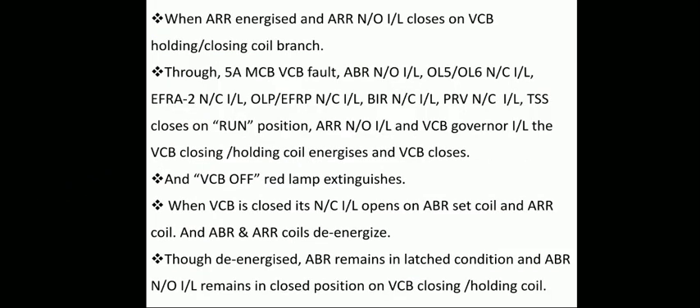When ARR energizes, its normally open interlock closes on the VCB holding and closing branch, parallel to the VCB normally open interlock. Through the 5-amp MCB for VCB fault, ABR normally open interlock, OL5 and OL6 normally closed interlocks, EFRA2 normally closed interlock, OLP and EFRP normally closed interlocks, BIR normally closed interlock, PRV normally closed interlock, TSS closed on run position, ARR normally open interlock, and VCB governor interlock — the VCB closing and holding coil energizes and VCB closes.